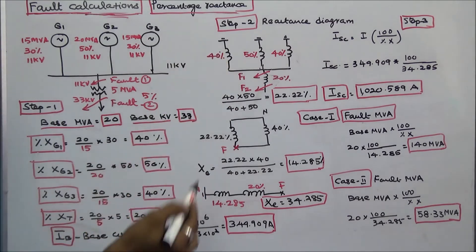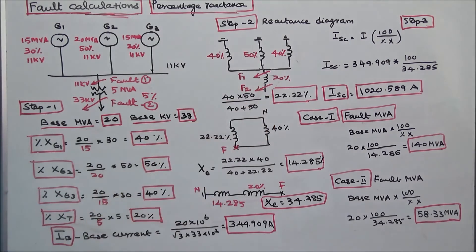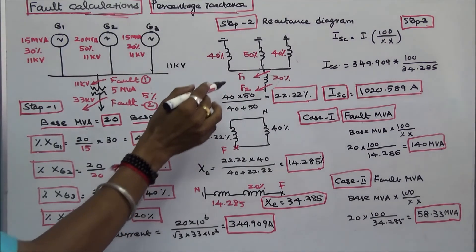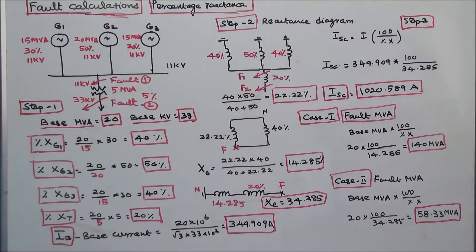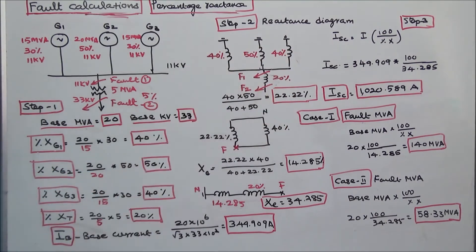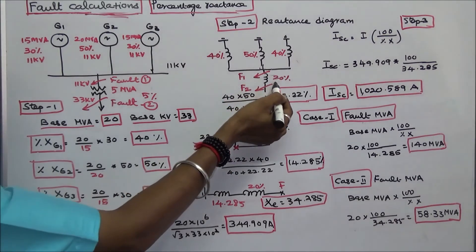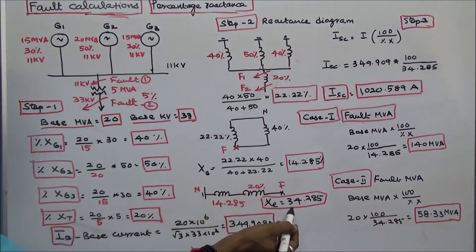Next, I calculate the total reactance between the neutral point and fault point F2. In the first case, we calculated the fault current at F1. Here, the three generator reactances are connected in parallel, giving an equivalent reactance of 14.285%. The 20% transformer reactance is connected in series with the 14.285%, so the total reactance between the neutral point and fault point F2 is 34.285%.